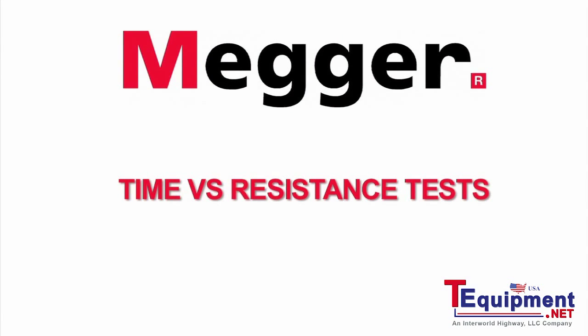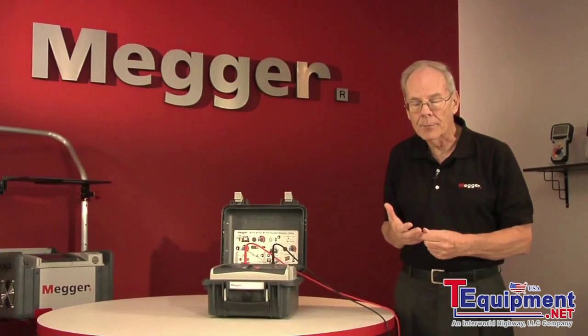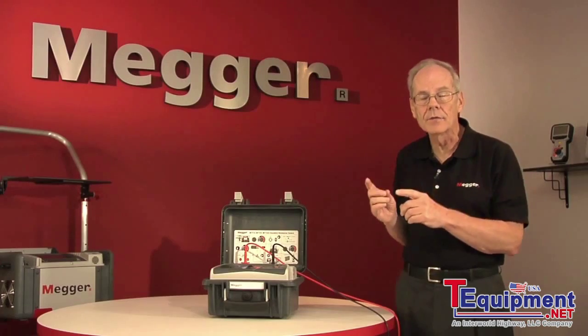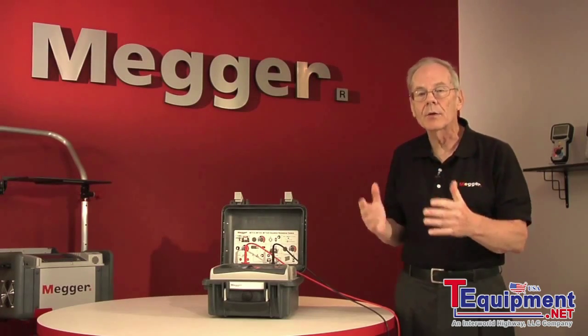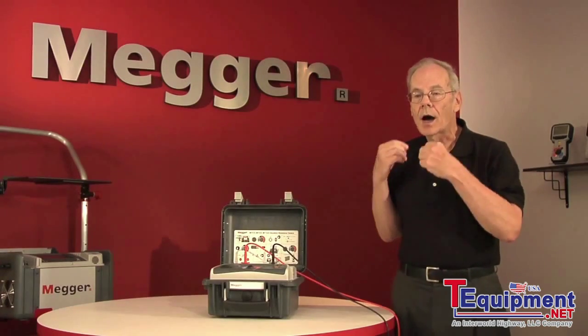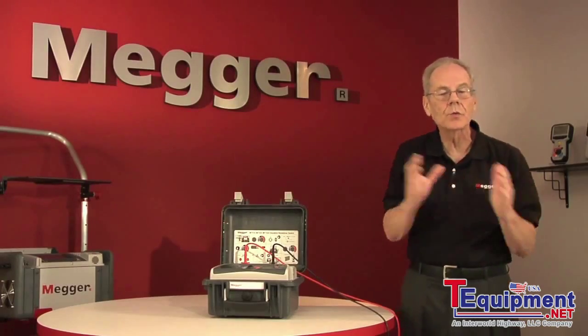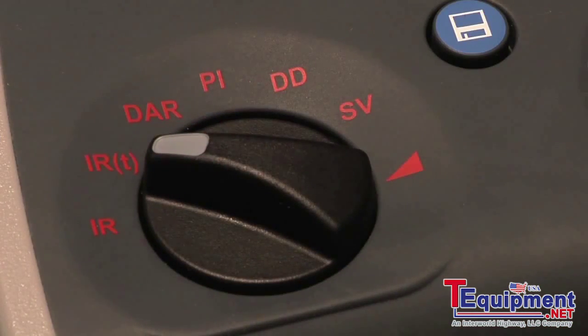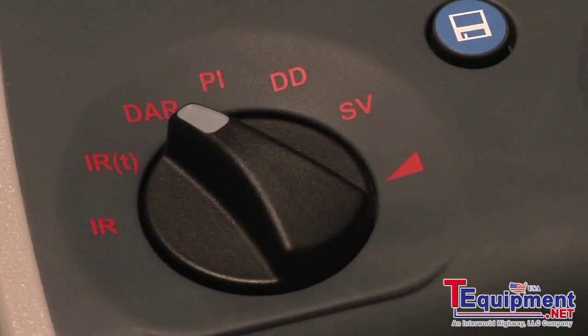These eliminate the dependency on the time of the test, the temperature effect, and also they give you a figure of merit which helps the operator interpret the test results as to whether he considers them good or bad. The selector switch also has a timer function for the insulation resistance test if you wanted to set that up. And the next position after that is the dielectric absorption ratio, time versus resistance.